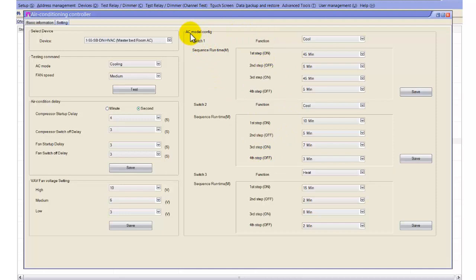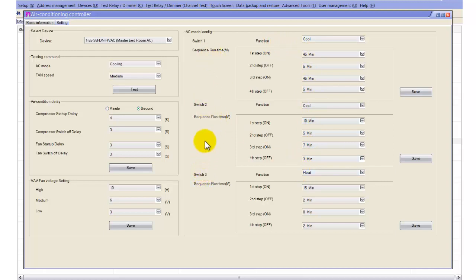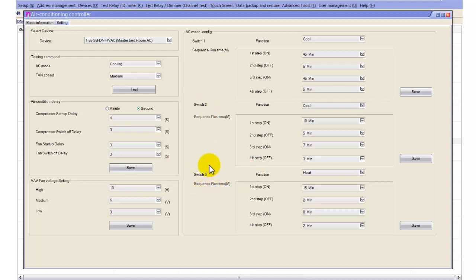Here we have AC mode configurations. In the AC mode, we have 3 outputs which you can configure as cool 1, cool 2, and heat. There are 3 switches because the module has 3 built-in relays. If you have 2-stage machines, you can use switch 1 and switch 2 for stage 1 and stage 2, and switch 3 for heating. If you have only a single stage, you use just the first 2 functions.